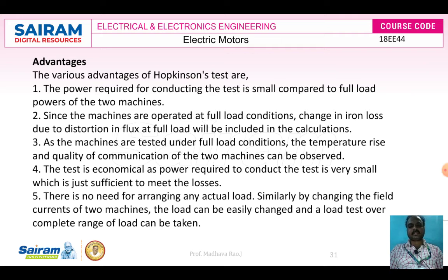As the machines are tested under full load conditions, the temperature rise and quality of commutation of the two machines can be observed. The test is economical as the power required to conduct the test is very small, just sufficient to meet the losses. So these are the advantages.